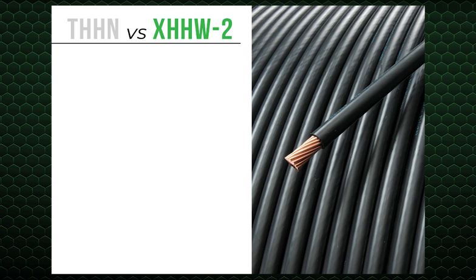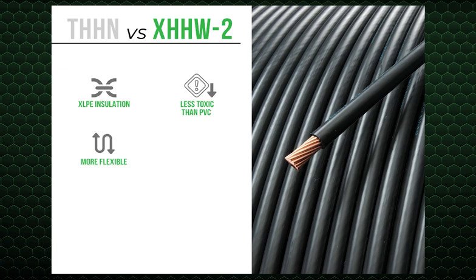XHHW-2 is a thermoset product. Crosslink products like XHHW have XLPE insulation instead of PVC, which is more resistant to chemicals, ozone, and abrasions. Because of the chemistries involved, modern XLPE is far less toxic than PVC in the event of a fire. In most applications, thermosets are more flexible than thermoplastics and are more advantageous for products where complex, close-space bends are required. Thermoset compounds utilize a curing process which causes a chemical reaction, allowing the polymers to cross-link. Once cured, thermoset compounds retain their shape and will not remelt when heat is applied.